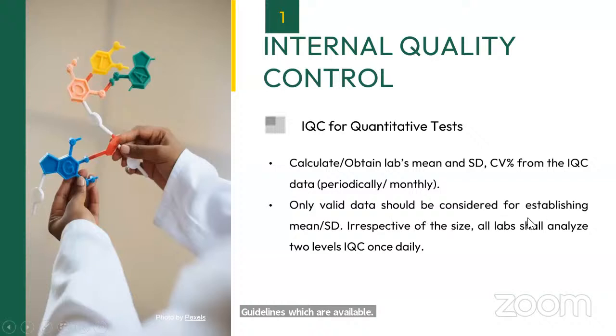Only valid data should be considered for establishing mean and SD. Whenever you are running the samples or QC materials, many times you will get outliers or quite abnormal values. Those data should not be used while calculating your mean and SD. Only valid data which is within the manufacturer's recommendation. Whenever you are buying a QC material, first of all, you have to use the manufacturer recommendations, whichever ranges have been provided by your manufacturer. And in those intervals provided by the manufacturer, if there are any outliers, you should not use those data for calculating your mean and SD.